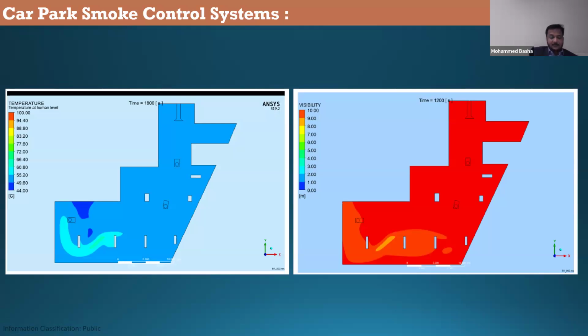If you can, try a CFD simulation with only 6 air changes, even in fire mode with all the scenarios, and you will be clearing the smoke in 1200 seconds. So what is the concept of an engineered smoke control system? You need to engineer it. It is not pre-engineered. Pre-engineered is the one which you take from the shelf and apply. But for an engineered smoke control system, they don't give you any parameters. You need to engineer a system, and that engineered system shall satisfy the criteria.